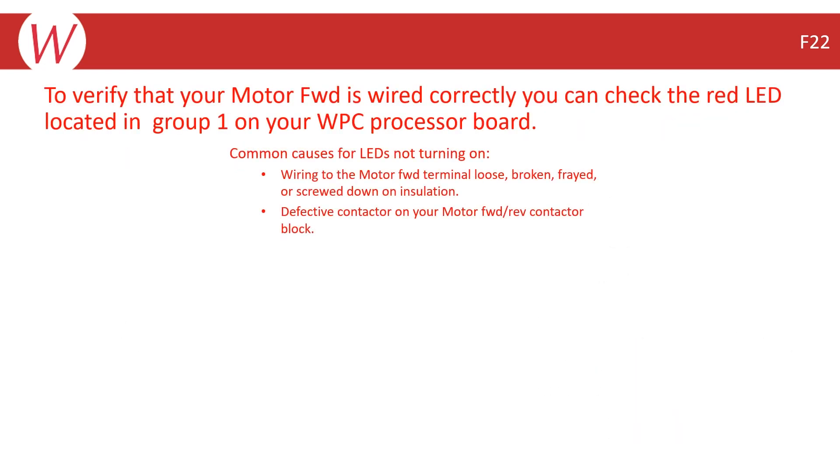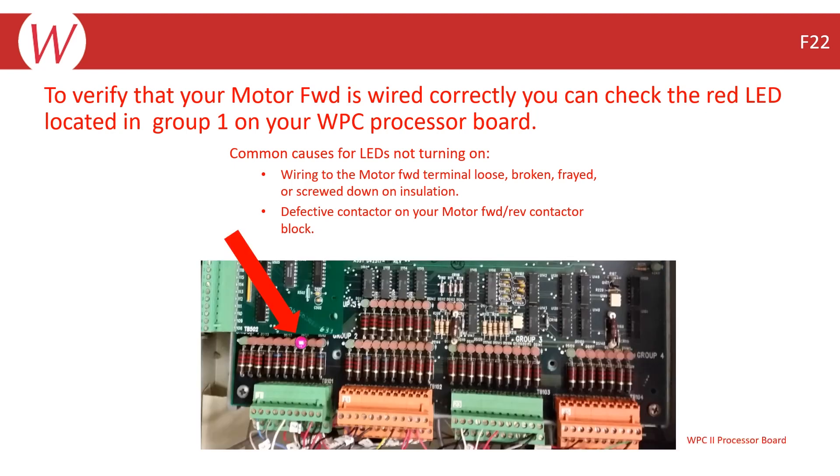To verify that your motor forward is wired properly, you can check the red LED in Group 1 on the WPC II processor board. As long as you cleared lockout and turned the motor on, the red LED in Group 1 will be on. This should stay on solid and not flicker at all. You can measure the voltage on Terminal 7 and should see a solid 24 volts DC.